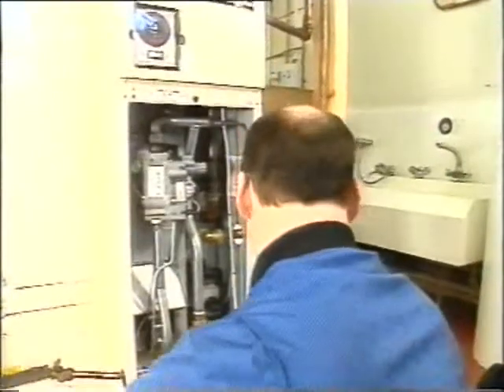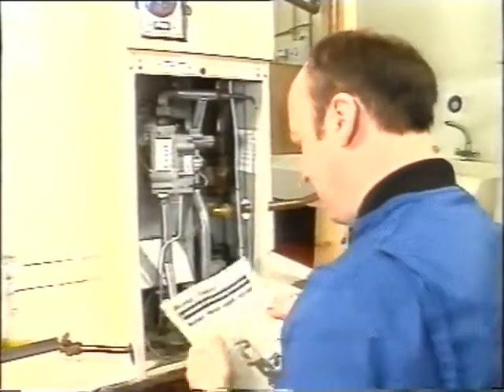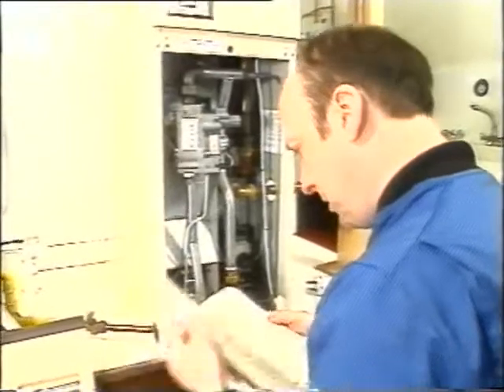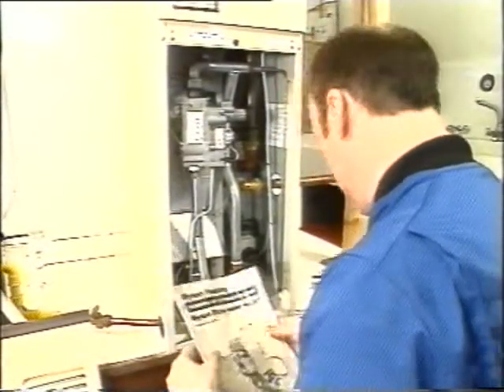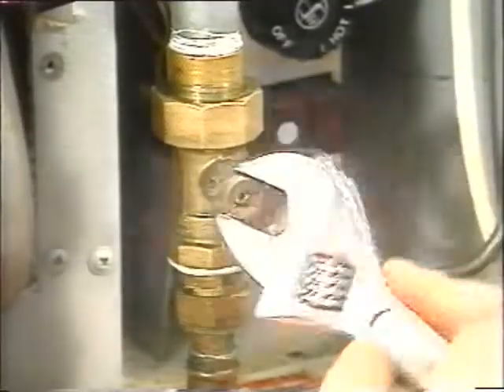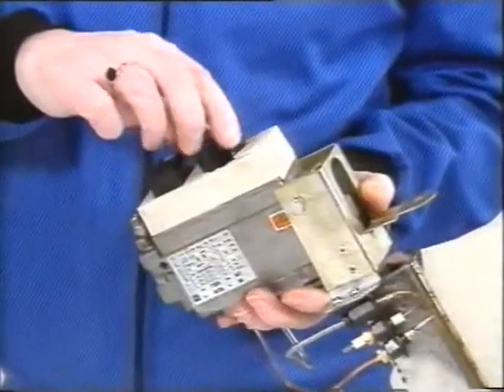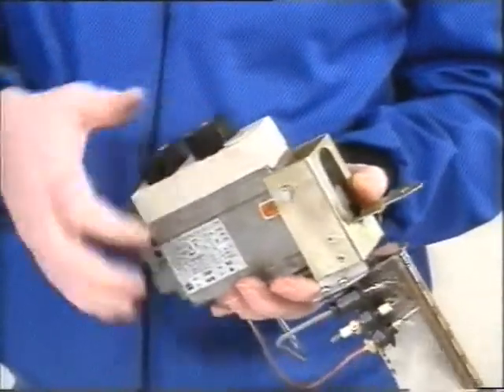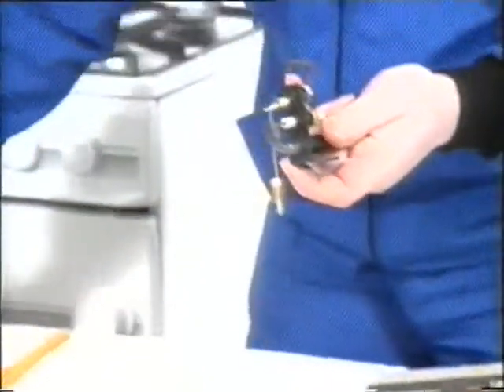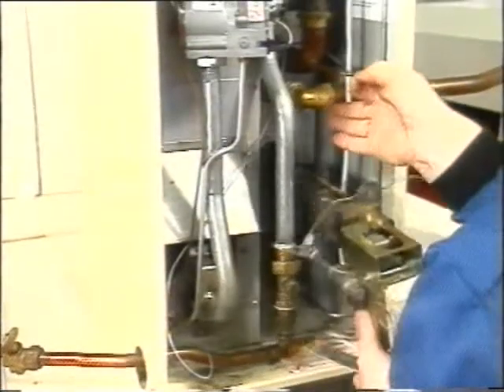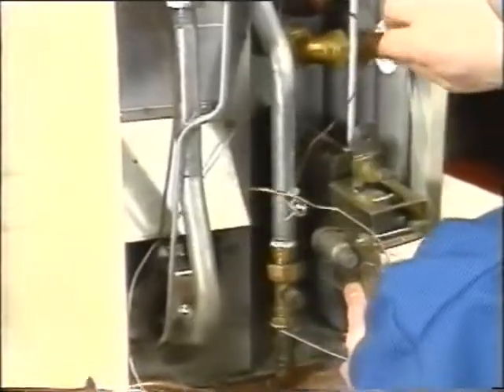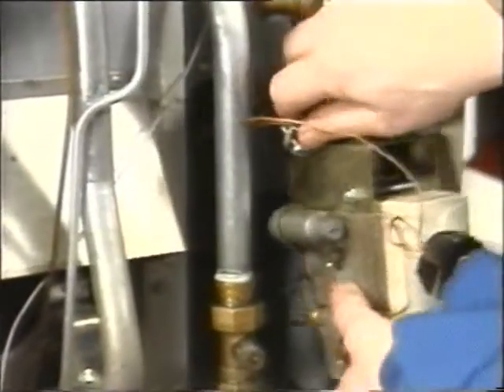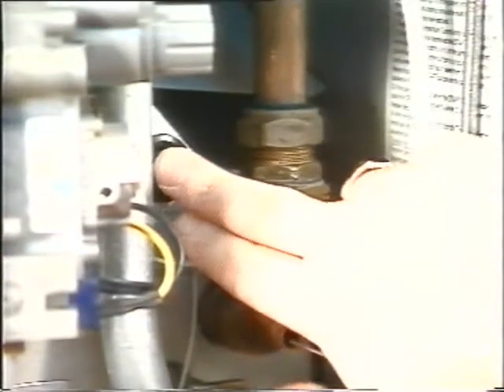Servicing is a logical process. First, check that the appliance complies with regulations and make sure that it works. Then turn off the gas service valve. Check the gas control valve and grease it if necessary. Remove and clean the main burner and the pilot. Clean the injector and the heat exchanger flueways. Put it all back together and test the gas installation for soundness. Now check the ignition and flame safety devices and the pilot flame.